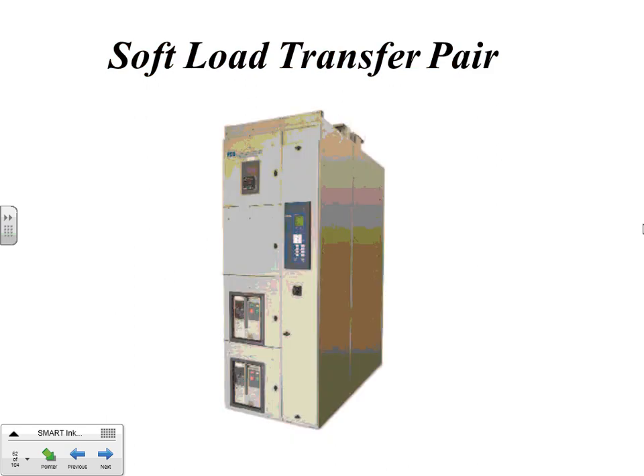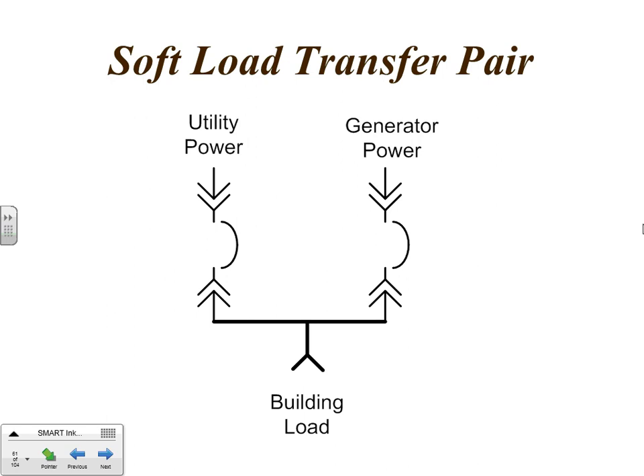If I may inject one thing here, next project that we want to do, we're going to have a 4,000 amp switchgear, and we're going to be using this method, soft start parallel switchgear. Okay. So just what we're using right now, Jerry, is we're using an auto transfer switch. We're bringing the service to the auto transfer switch, so we need a service disconnect means. That's the project that we're doing. We have a 500 amp building, feeding it to a gen and the service via an auto transfer switch. So bringing the service right into the auto transfer switch. So, service entrance rated switch. Yeah.